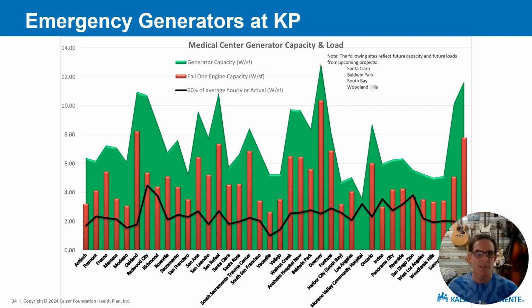So the chart that you're seeing here shows the generator sizes at all of our facilities. The y-axis is in watts per square foot. And you'll notice that the total installed generator capacity varies wildly from 3.5 watts a square foot up to 13 watts a square foot. We call this the Christmas tree chart, by the way. The green line or area there shows the generator capacity at each facility, and then the red bars show the capacity at the facility if one generator failed to start. In the unlikely event that one generator failed to start, it's simultaneous to that power outage. The black line at the bottom there shows our estimated loads.